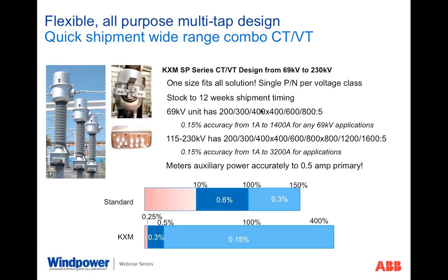Another development that has been extremely important is that we all know that lead time is critical to wind farm development, and the quicker the better. And in most cases, lead times on development of wind farms are far shorter than some of the product lead times themselves. So a way that we as a manufacturer have been able to overcome that concern is we've developed an all-purpose, standardized design, multi-ratio unit with the wide range high accuracy incorporated.